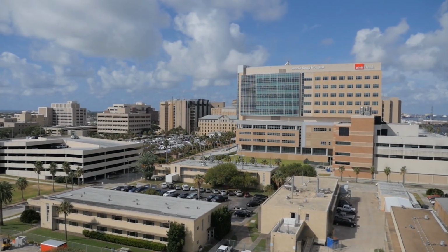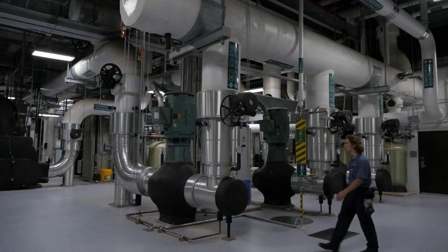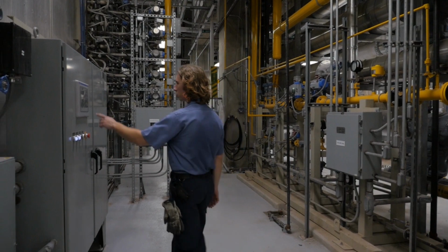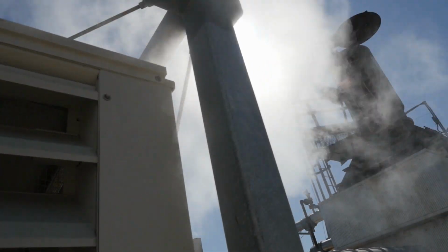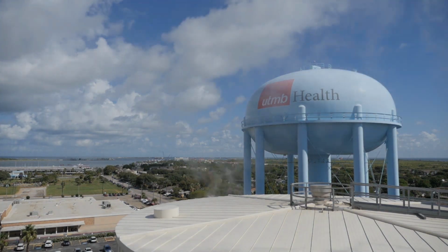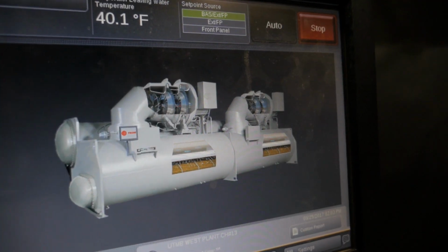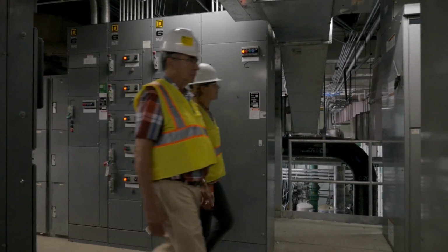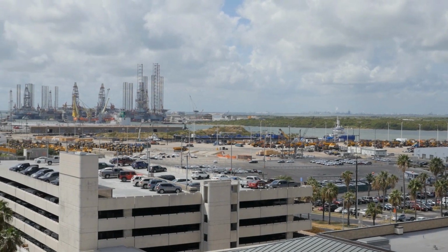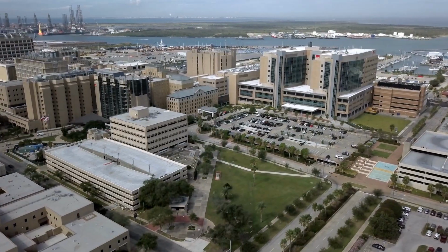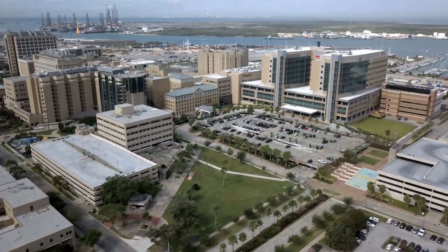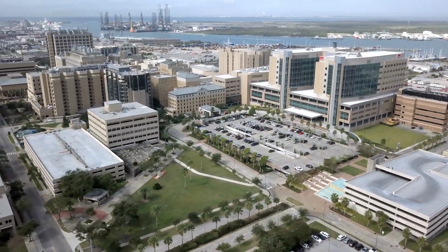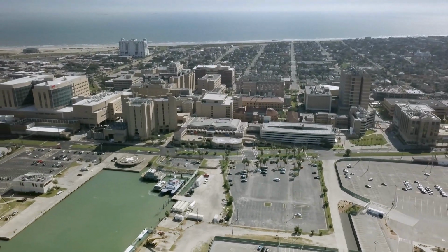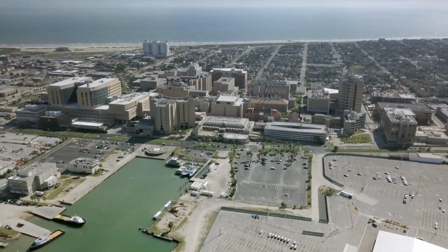One of the requirements of the university was not only for this to be resilient, but to make good business sense. And when you have 15 megawatts of grid-connected capacity in a deregulated market, you can take advantage of economic dispatch. And when the grid is suffering, or when there's a shortage of capacity, or there's an unexpected outage, and real-time market prices we've seen go as high as $2,000 or $3,000 a megawatt hour, our ability to not only take load off of that grid, but actually dispatch into that makes a tremendous amount of economic sense for the institution. We're prepared to be able to run this institution's air conditioning for an entire week without municipal supply.